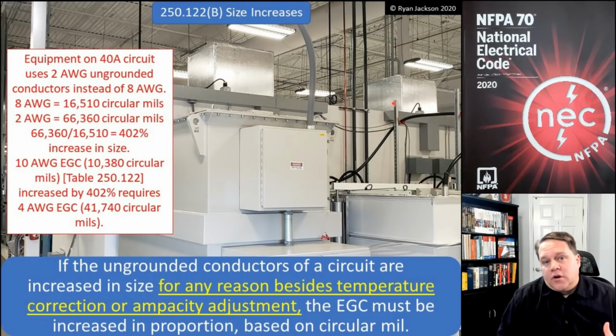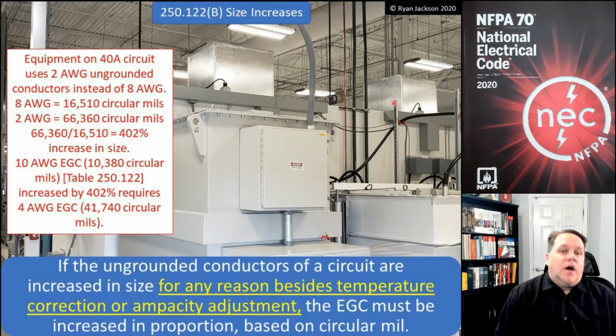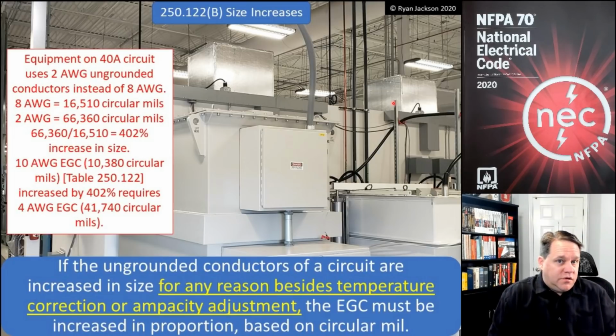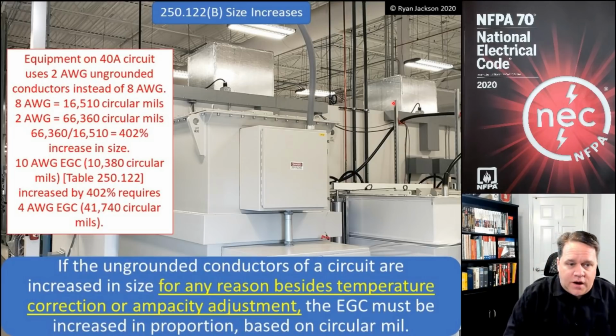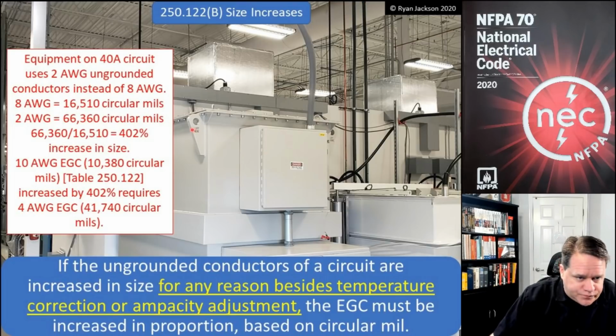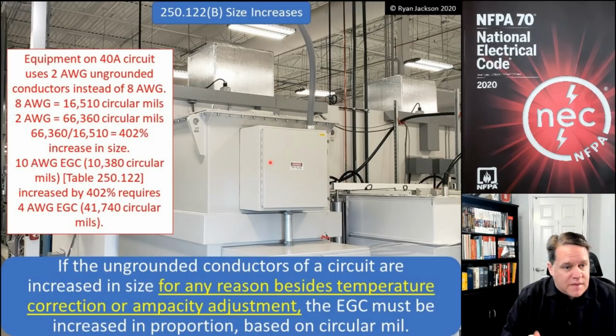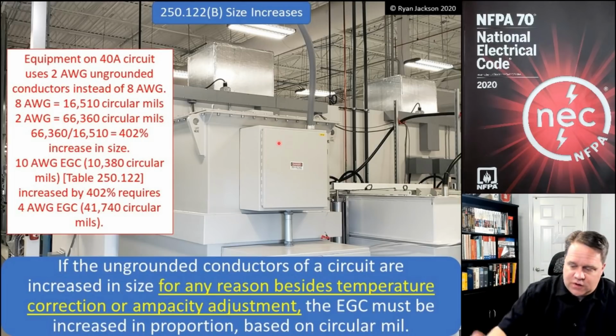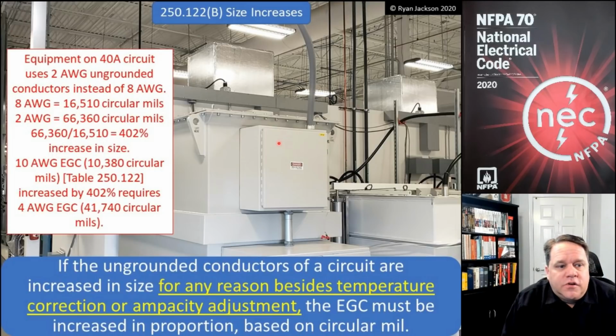I would find the circular mil of my 8 gauge wire, which I could have used, but for the voltage drop. I find that circular mil and I write it down, 16,510. Then I find the circular mil of the conductors that I actually installed. 2 gauge conductors are 66,360. So then I would do the math, and I realized that that is an increase of 402%. All right, so write that number down, 402%.